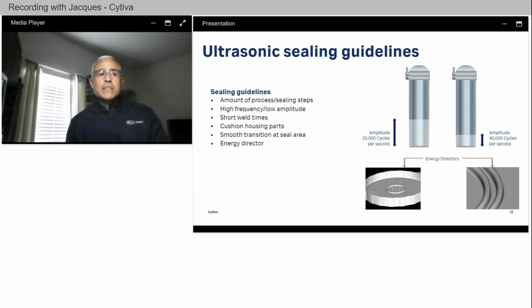We recommend sealing to an energy director rather than a wide, flat surface. These energy directors should have a radius to avoid a sharp edge that may damage the filter membrane when ultrasonic welding the membrane directly to the housing component. You can see from the pictures on this slide that there are radiuses on the tops of each of these circular energy directors. And lastly, successful ultrasonic sealing requires the user to optimize the equipment's frequency and amplitude during process development, and then ensure these conditions can be sustained during production.